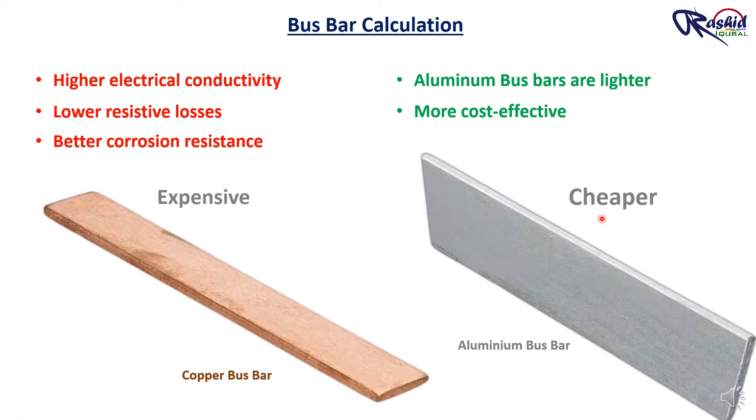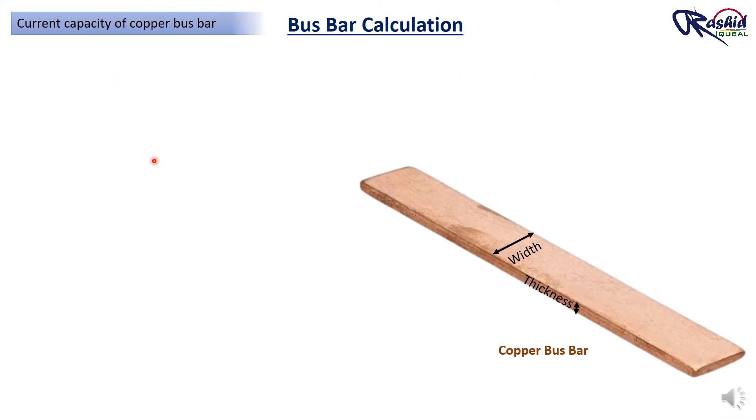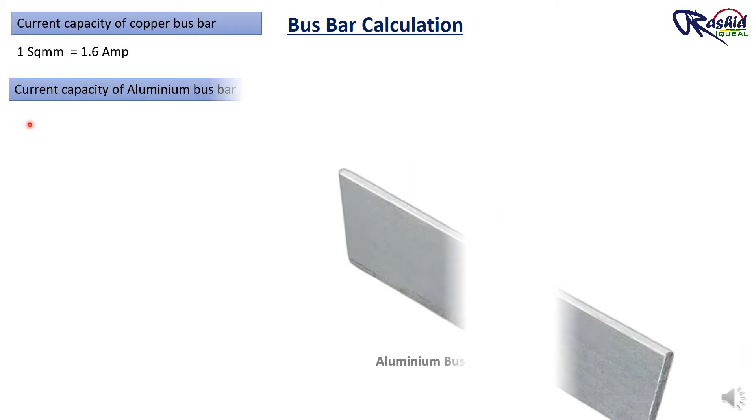When considering copper conductor, the current carrying capacity of 1 square mm of copper is approximately 1.6 ampere. For aluminium conductor, the capacity of 1 square mm is around 0.8 amperes. While these values can vary based on the quality of material, we can consider this value as a thumb rule for the busbar calculation.